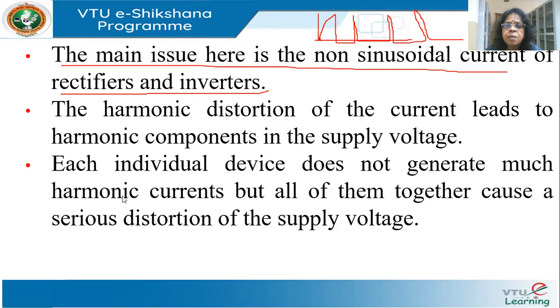So all these equipment are the main source and cause of harmonic distortion of the current. These harmonic currents cause voltage drops -- what is a voltage drop anywhere? It is I into Z. Z is just a number, right? I is non-sinusoidal, therefore IZ will also be non-sinusoidal. So these harmonic distortions in current also cause harmonic distortions in voltage.